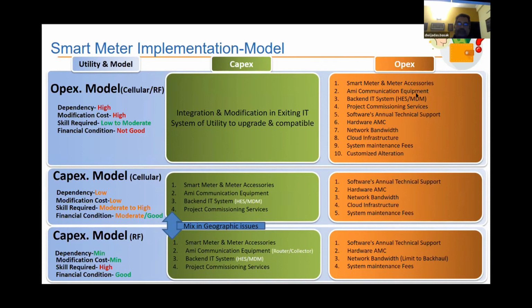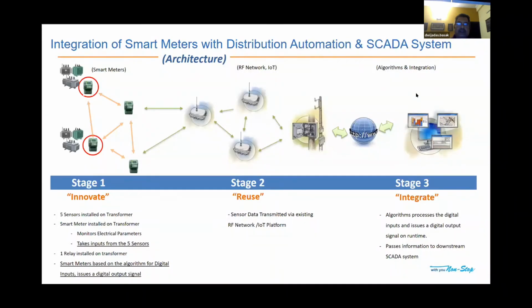Next slide, please. Here we have tried to show a use case where we are introducing the DI-DO concept. Basically, we have installed sensors in the transformer to monitor its health, like oil level, oil temperature, cover open, and other parameters — five sensors independently monitoring separate parameters of the transformer.